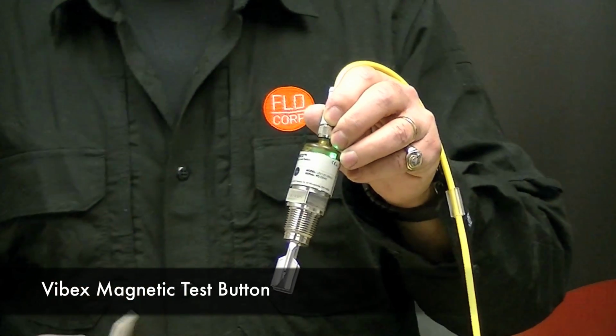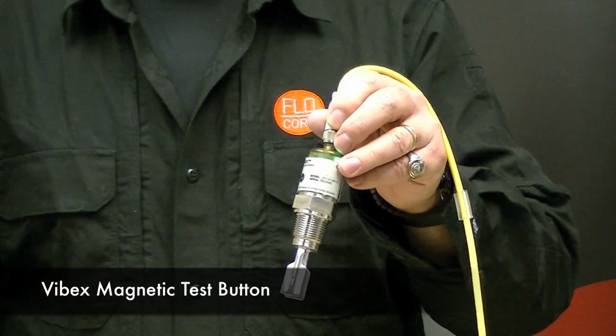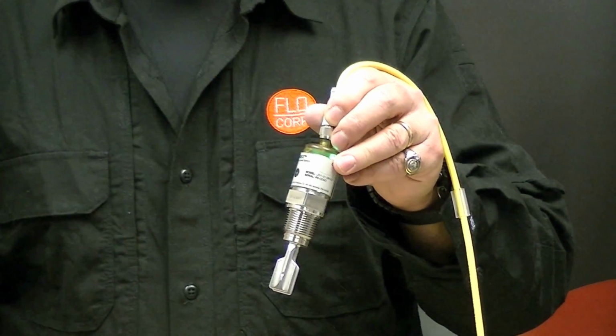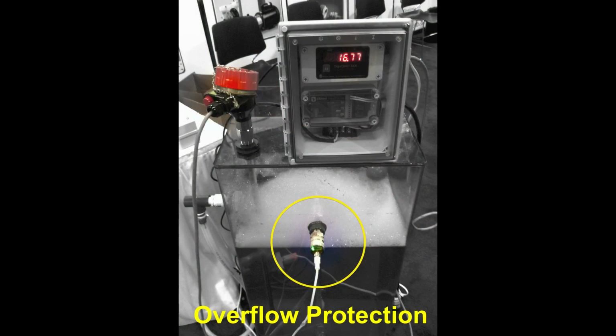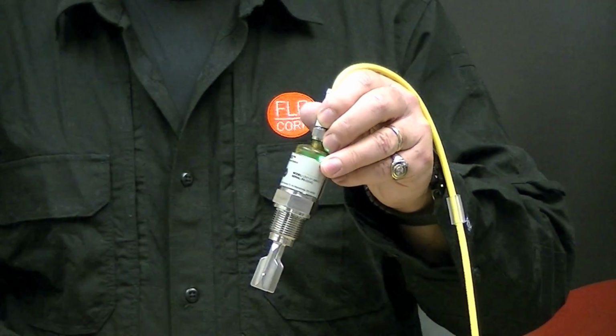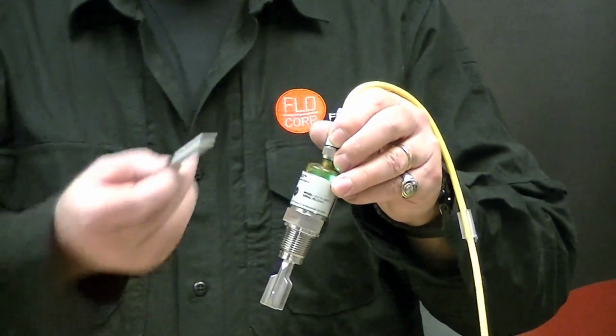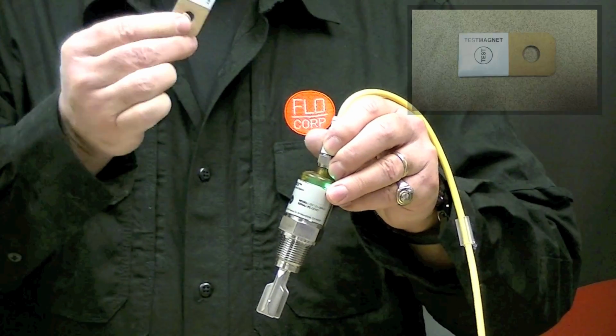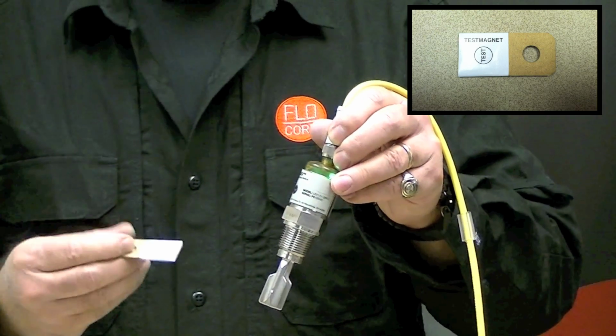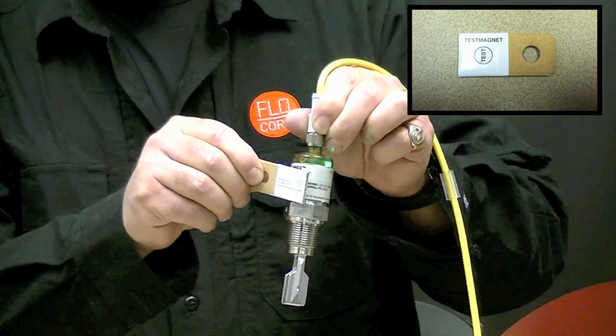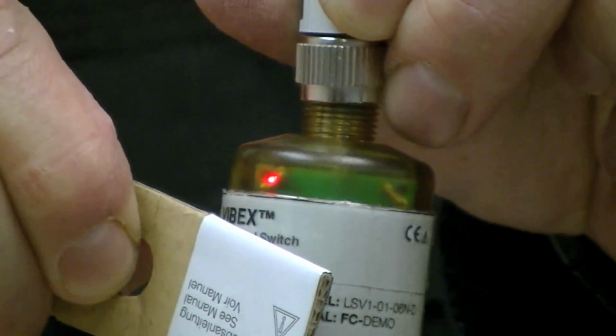The Vibex can also be used for dry pump protection, high-level tank protection, for overflow prevention, and in that case the Vibex may not be operated for months or maybe years at a time. In this case, you may want to just test the Vibex just to make sure the circuitry is still intact. You'll notice in the demo kit that there is a test magnet. This test magnet can be put over the Vibex, and you can see the switch point change.